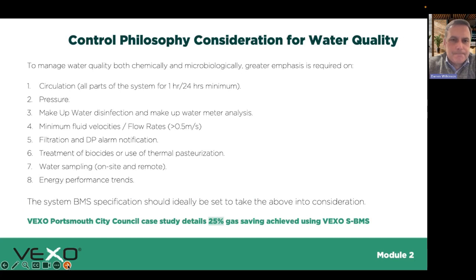So, circulation—think about the pressure in the system, the incoming water quality, flow rates, treatment of any biocides, or you can use thermal pasteurization sometimes depending on the system. Certainly think about your water sampling, on-site and remote. There are a lot of emerging technologies now; one's been around for a while—a company that does remote monitoring of corrosion, which I think is really good. Depending on the size of the project, if you can justify it, that'd be a huge bonus for your client, the building owner ultimately. But yes, keeping water quality clean with the right level of controls.